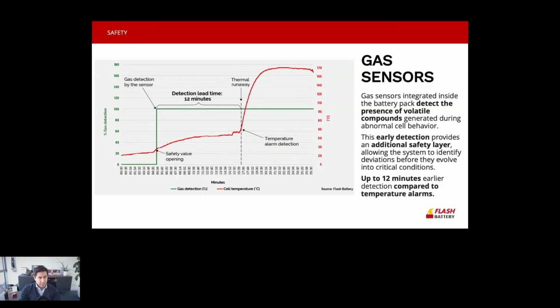The battery pack normally can operate up to 60 degrees. It means that if we see a temperature increase, we cannot set up an alarm at 35 or 40 degrees. We need to see a big increase in temperature, which means we have to wait.